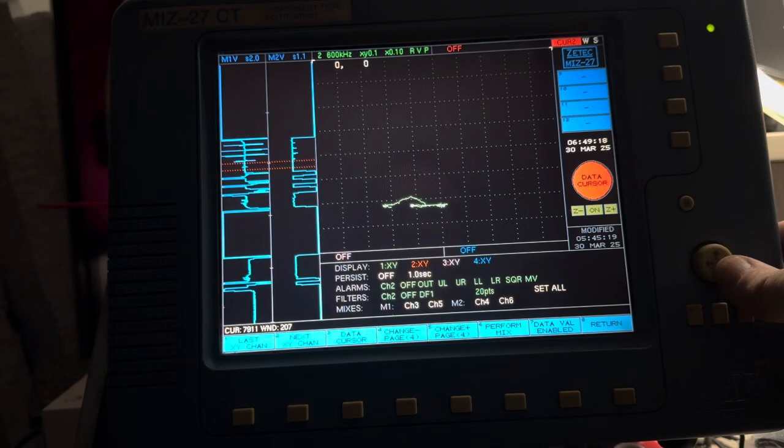My impedance is changing just with probe wobble, because anything that changes the coil properties is changing impedance, whether that's fill factor, lift off, dents, bulges, flaws, deposits on the outside of the tube support plate. Anything that the probe sees is changing test coil impedance. And when I move over a flaw, when I load the coil with the test material, that's taking energy away from the coil, and it lowers inductive reactance and lowers impedance.